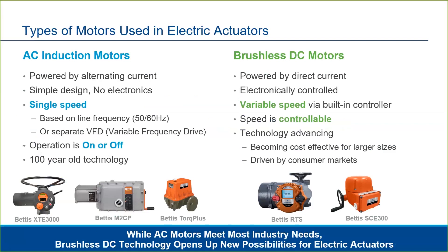DC brushless motors are powered by direct current. This simply means that DC current is used internally by the motor controller. The actuator itself can still accept line power in either three-phase AC, single-phase AC, or DC. DC brushless motors are controlled by a motor controller, which takes the power signal and varies both frequency and amplitude of the current to the motor, thus providing the ability to adjust the speed and torque of the actuator output.